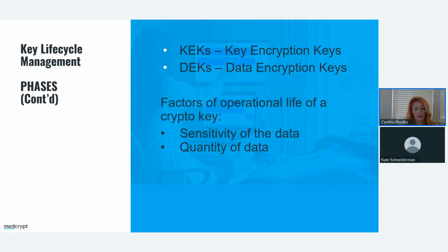Keys are fundamentally used for encryption of data on the medical device ecosystem, but encryption often functions as a very ubiquitous proxy for other implementations such as authentication and signing. You can actually prove who you are based on ownership of a key. Once a key is generated, the key management system should manage the chronology of conditions that a key progresses through over its life cycle and enable an authorized administrator to operate them when required.